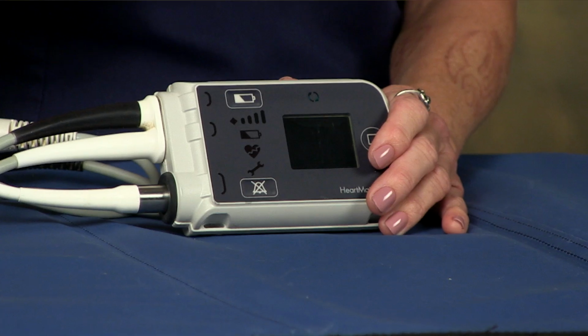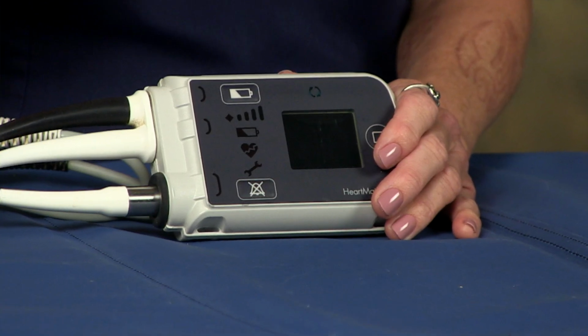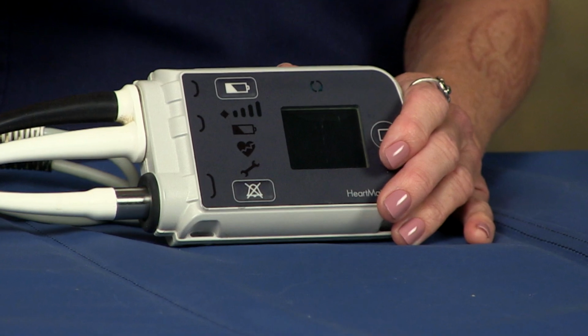If the driveline disconnected during transport, connect it. Remember that HeartMate 3 has 2 connection points. If the connections are secure, check for damage. If the driveline was disconnected before you arrive and the patient is tolerating, call the VAD coordinator immediately. If the patient is not tolerating either of these red heart alarms, CPR or defibrillation may be needed. Again, the VAD coordinator must be called to assist with troubleshooting and patient management.